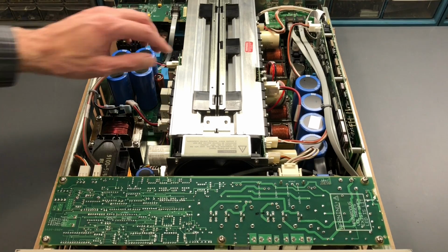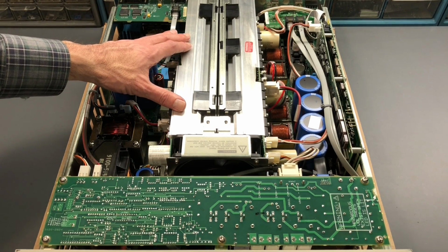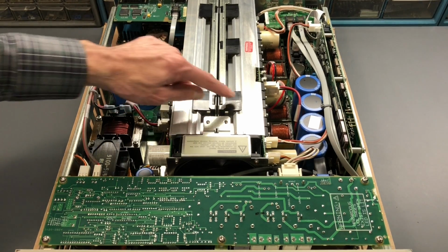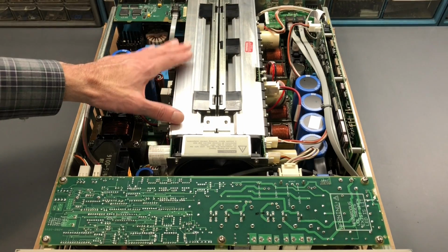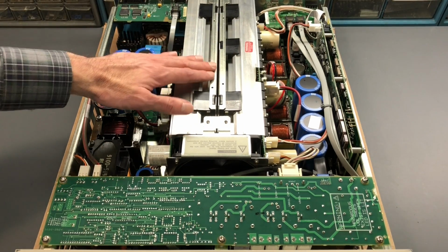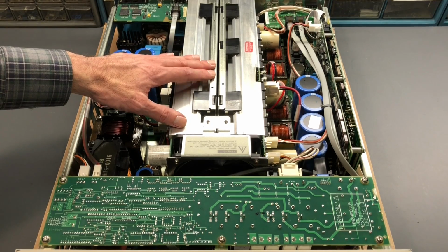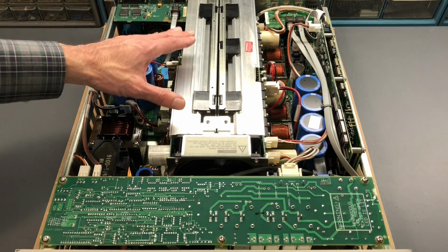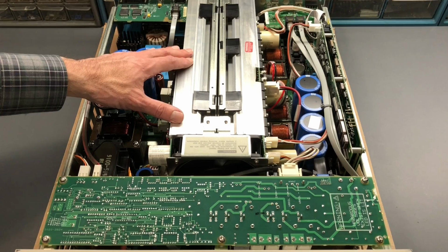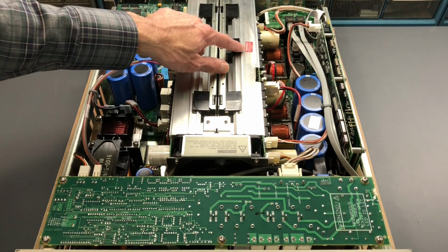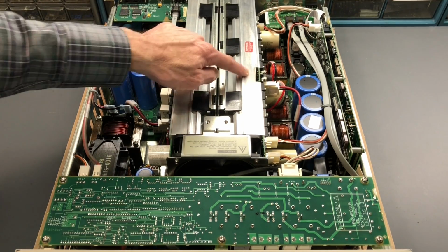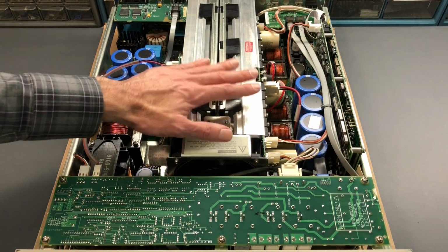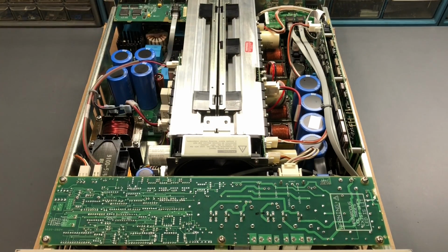Now you can see these heat sinks are electrically insulated from the chassis, so these plastic clips right here are holding these heat sinks away from the metal support brackets that are of course at ground potential, meaning that these are electrically floating and can be electrically live, and there actually is a notice right here that this surface may be electrically hot. So you'd never want to reach and touch these when this is actually powered up because you could get a shock on those heat sinks.